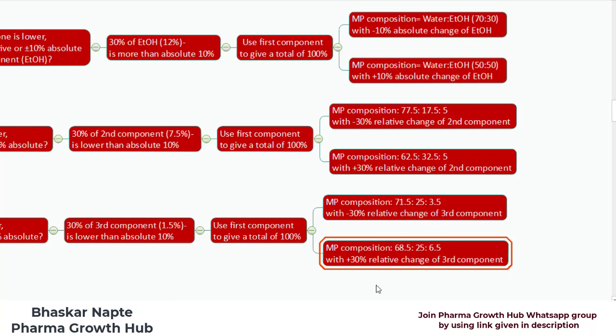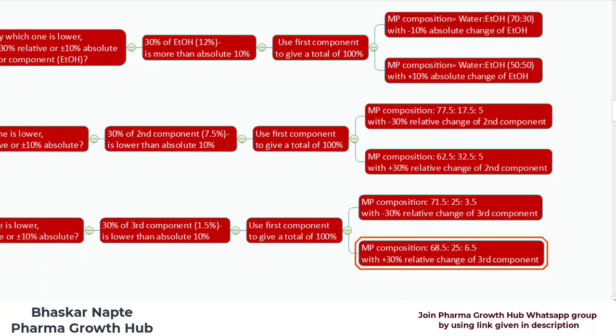The second possible mobile phase composition with plus 30% relative change of the third component is 68.5 : 25 : 6.5. I have added 1.5, so 5 plus 1.5 becomes 6.5. I haven't changed the composition of the second component. As the quantity of the third component increased by 1.5, to balance it out I need to decrease the quantity of the first component by 1.5. The original quantity of the first component is 70, so 70 minus 1.5 becomes 68.5. This is how we understand the allowable variation for a ternary mixture.